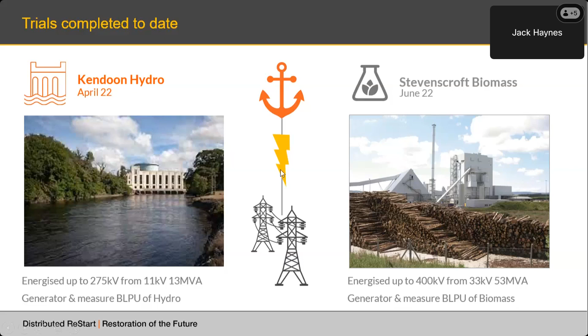But what we hadn't had the opportunity to demonstrate was an inverter-driven, non-synchronous machine acting as the anchor generator in the power island. That is where the extension to the trial, or the series of trials, as part of the Distributed Restart project came in. That was to utilise a battery energy storage system, in our case, to act as the anchor point and grow the power island to energise both the local distribution and transmission network, and also add an additional DER to the mix to act as the top-up generator.